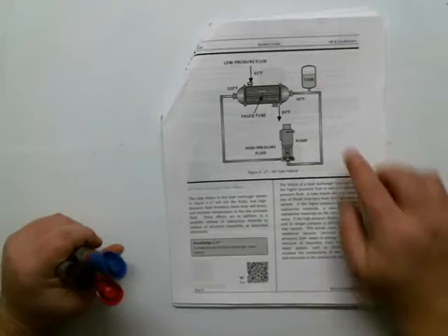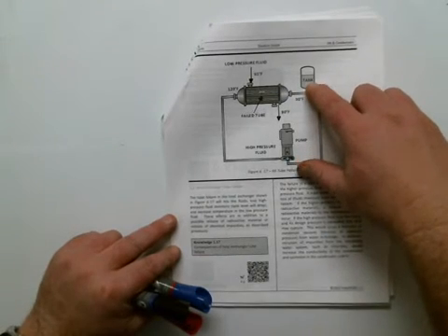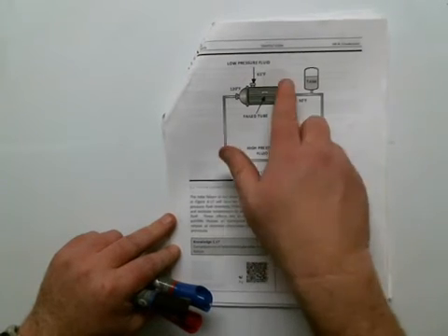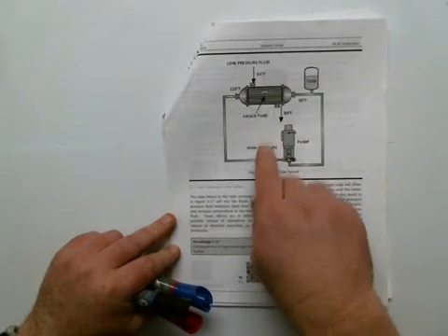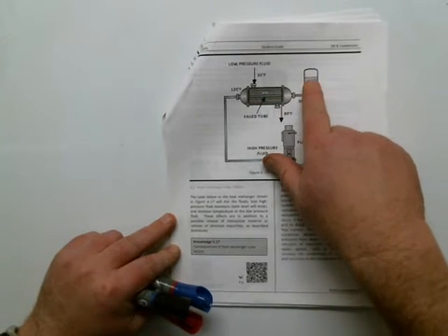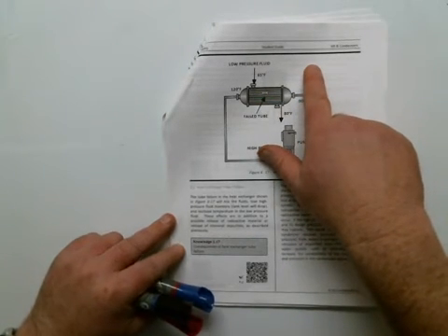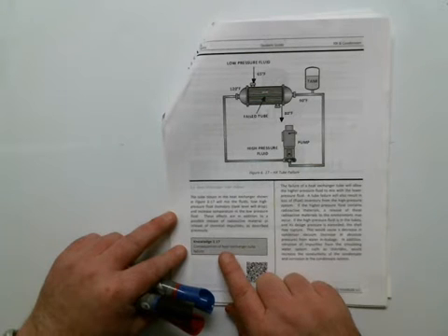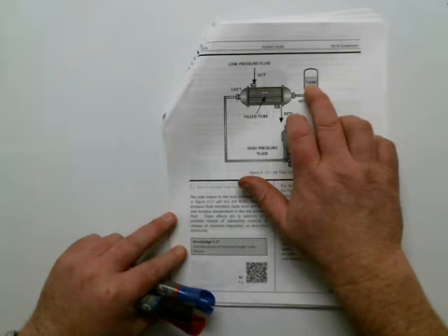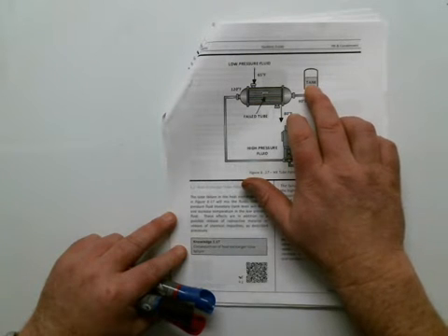So in this case, that's going to result in this tank level actually going down because it's on the high pressure fluid. Now, if we had changed these and we put this as the low pressure fluid, well, I know that the high pressure fluid would flow into this low pressure fluid and this tank level would rise. So you really need to understand this knowledge requirement, the consequences of heat exchanger tube failure, and what would happen to, say, a head tank that's in the turbine building or the reactor building.